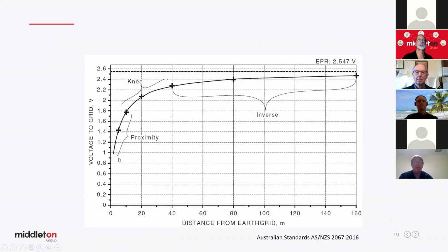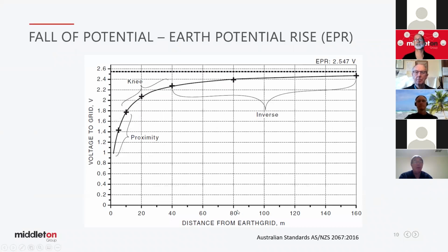Let's look at that curve now. In that situation, this is the distance we're walking away from the substation along the bottom, and the voltage that we're measuring. As we go further away from the substation, you'll notice the voltage that we're measuring is getting higher and higher. If we've got a fault level of, say, 10,000 amps, and we're pushing 10 amps around our circuit that we looked at earlier, we quite simply multiply what we've measured here by that factor of 1,000. So in this particular case, we're getting close to, say, 2.5 volts. So an actual fault case of 10,000 amps would give the substation an EPR of 2.5 kV.